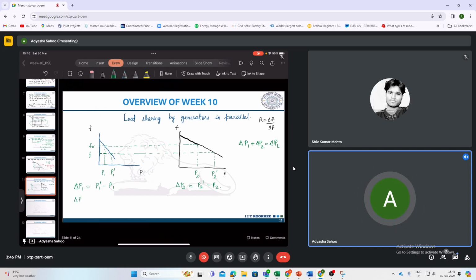And from the droop relation, we know also this delta P1 will be, see, R is delta F by delta P here, right? So delta P is delta F by R. So delta P1 is delta F by R1, and delta P2 is delta F by R2. So if we divide these two equations, what we will get? Delta P1 by delta P2 will be R2 by R1. That means the amount of load picked up by the generator is inversely proportional to the droop. What it means is that the generator with greater droop coefficient will pick less amount of load.